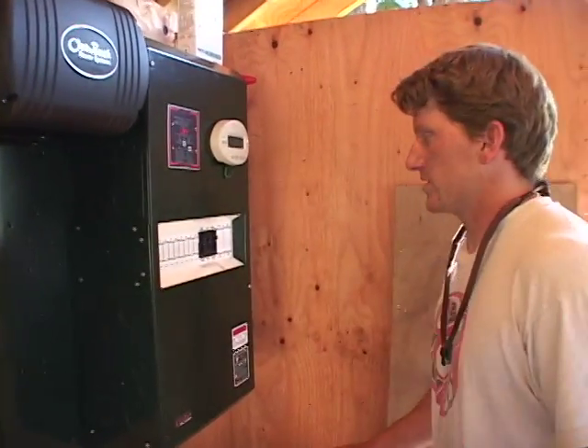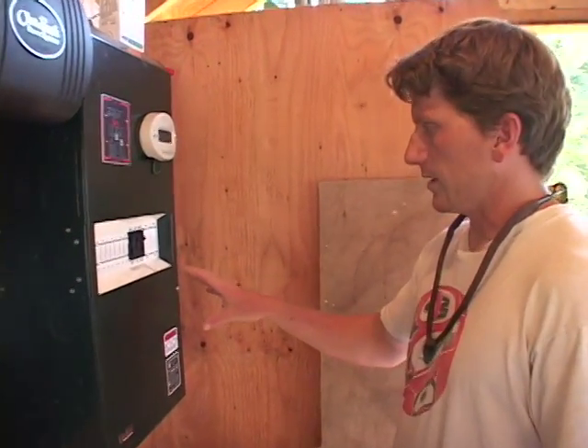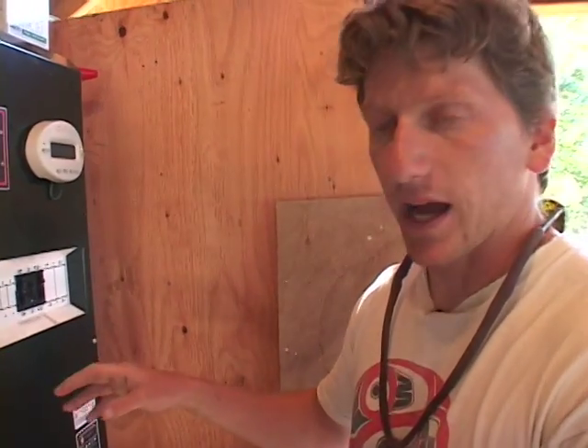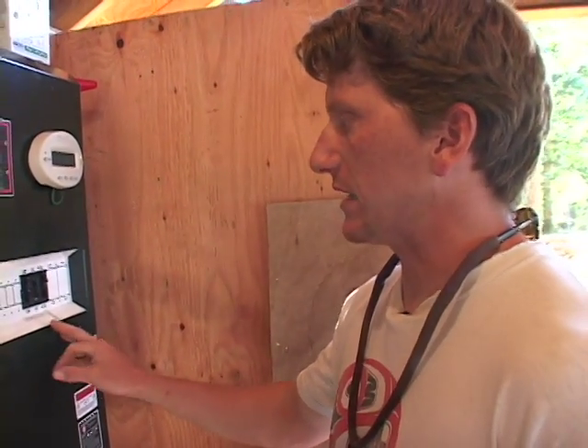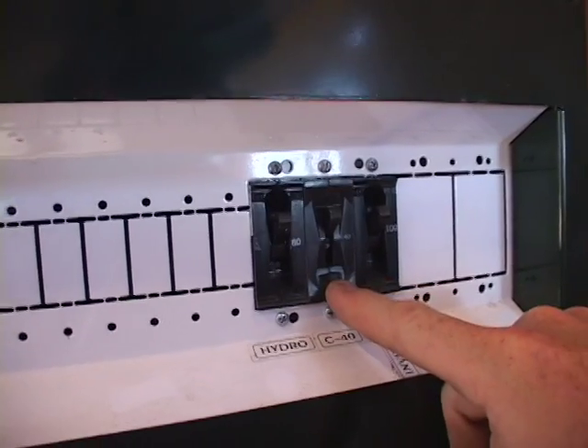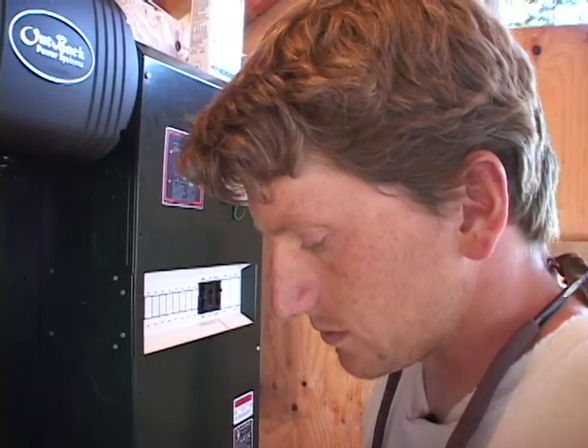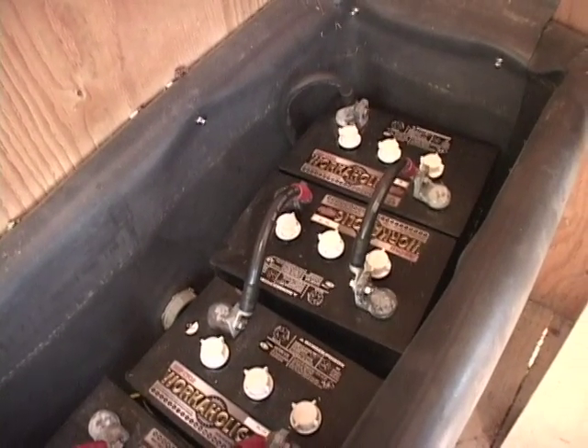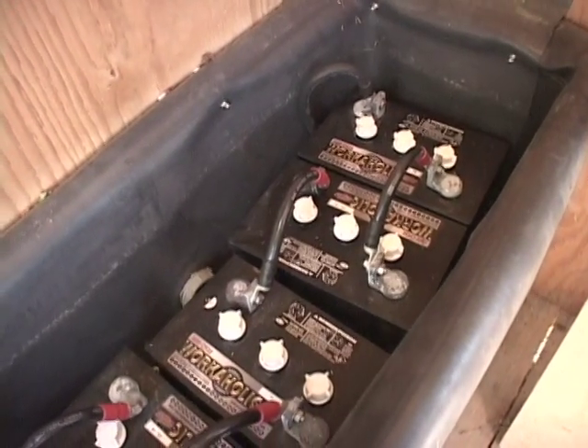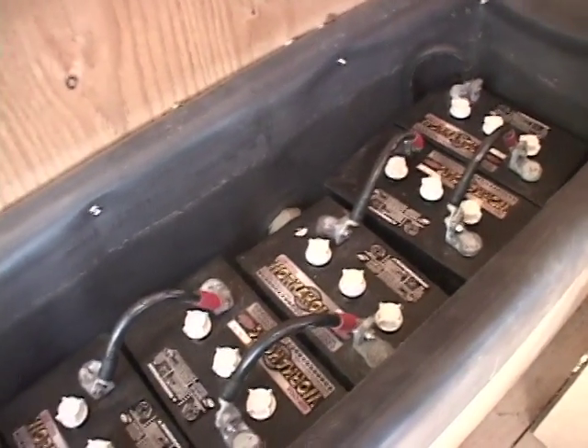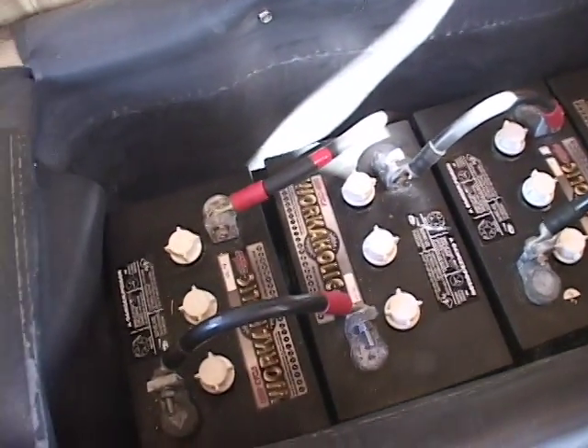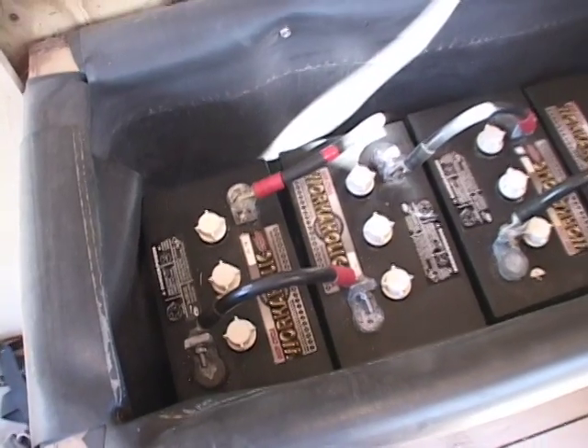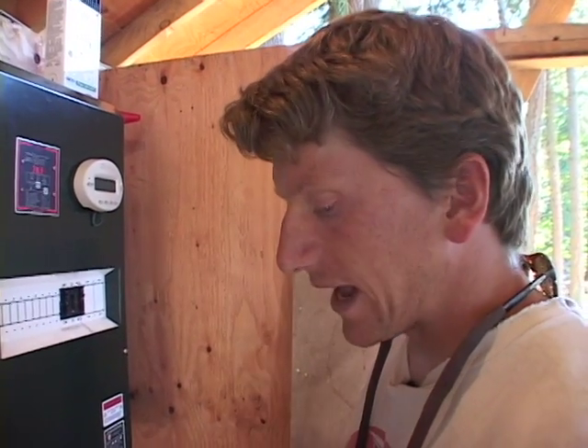So this is the power system equipment. The power comes up the hill from the hydro as 48 volts DC and comes through these circuit breakers, charging the battery. These are 6-volt forklift batteries, deep cycle lead acid batteries. They're 6 volts each, and I have 8 of them wired in series, positive to negative, to make 48 volts nominally for the whole bank.